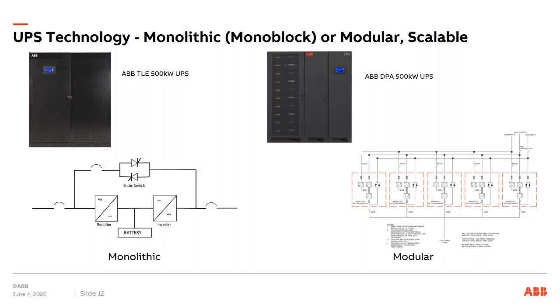So now, like the single line that I showed before with the UPS, that, like I said, is probably 99% of the UPSs out there. UPS manufacturers have come up with a number of different designs based on this design. And what we have today is a mix of what is referred to as a monolithic UPS, which is a traditional one, like that 185 kVA GE UPS, that was a monolithic UPS.